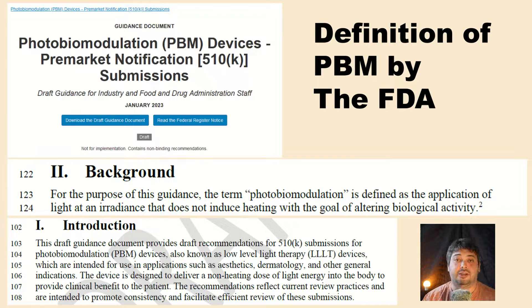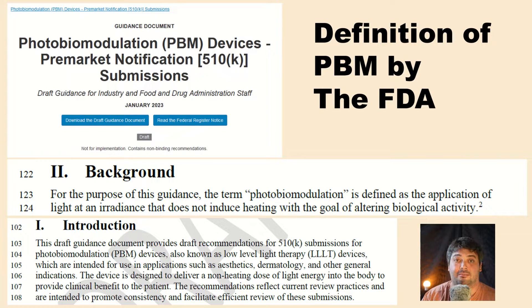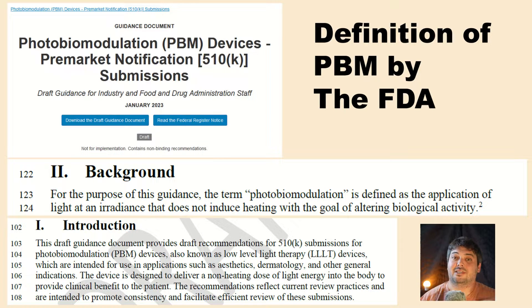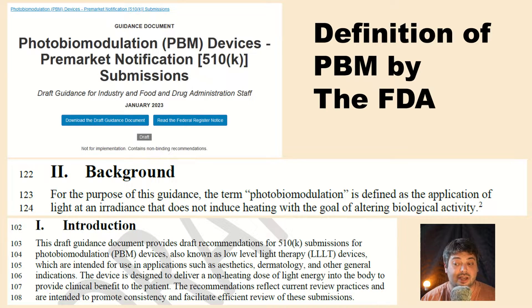A big step for mainstream approval was that the FDA issued a draft guidance for photobiomodulation device approvals last year. In this guidance, they defined the terms of photobiomodulation for devices they would approve. For the purpose of this guidance, the term photobiomodulation is defined as the application of light at an irradiance that does not induce heating with the goal of altering biological activity. They also state: the device is designed to deliver a non-heating dose of light energy into the body to provide clinical benefit to the patient.